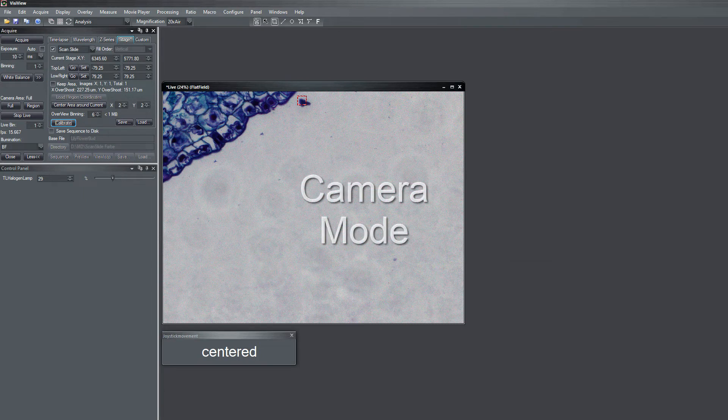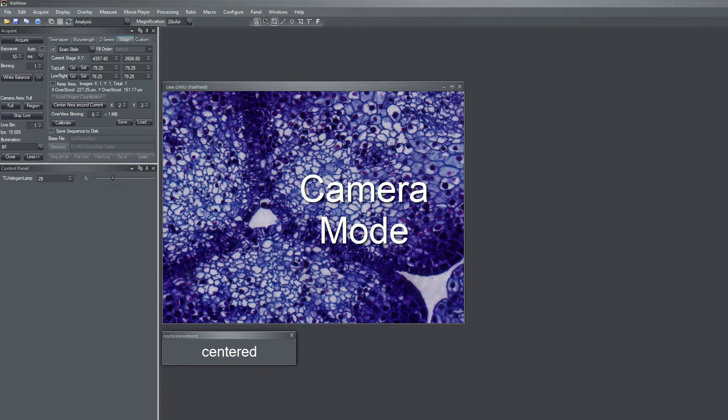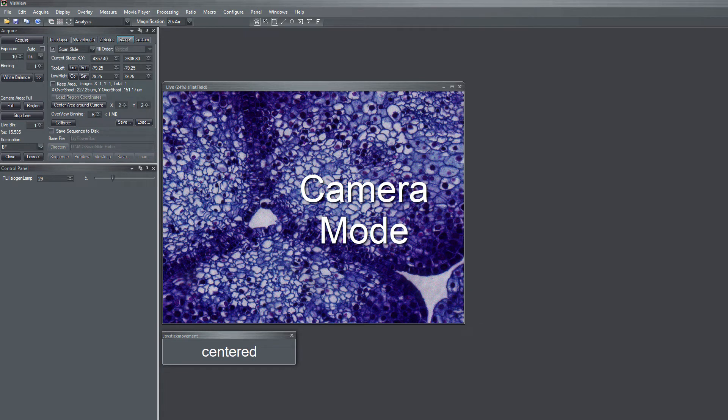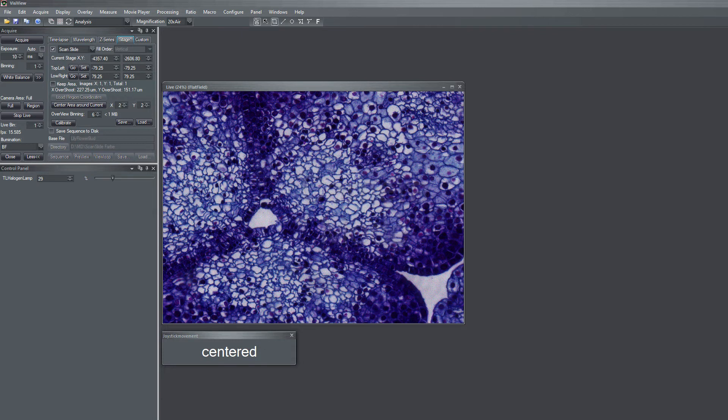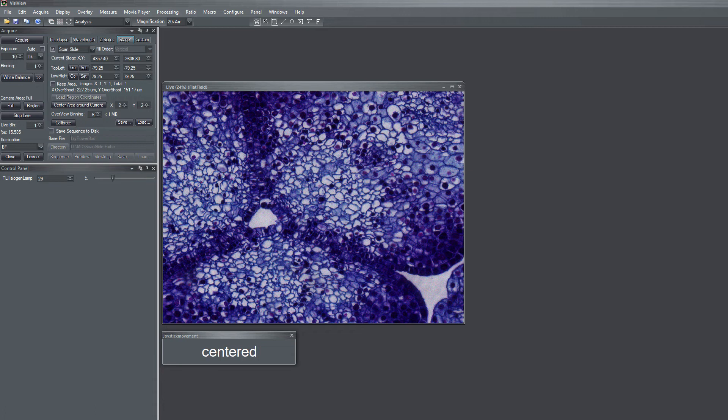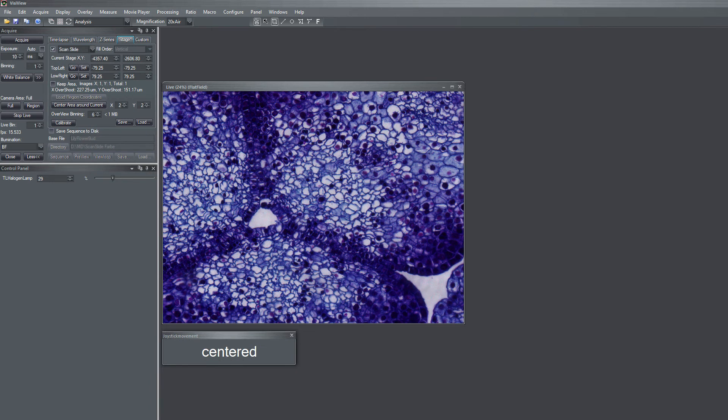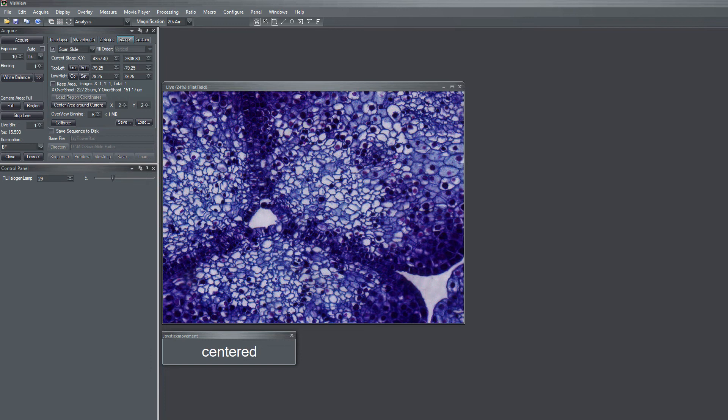Before I told you that you can run the scan slide also in camera mode. For the camera mode, you have to rotate the camera by 180 degrees physically, or you go to camera configure and invert both the flip and the mirror direction. If you then also invert the polarity of the motor steps in the x and y-axis in the configure devices of your stage, then you are again ready for scan slide calibration.